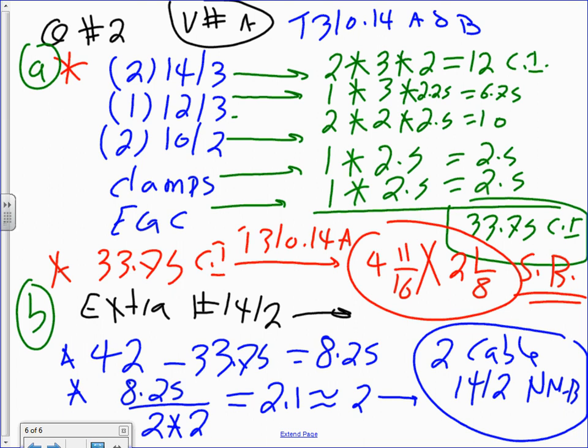The first 2 is for the number of conductors, because there are 2 conductors in the cable. The second 2 is the allowance for number 14. If it was number 12, it would be 2 by 2.25. Any comments on how to do a box fill calculation? This is for A.